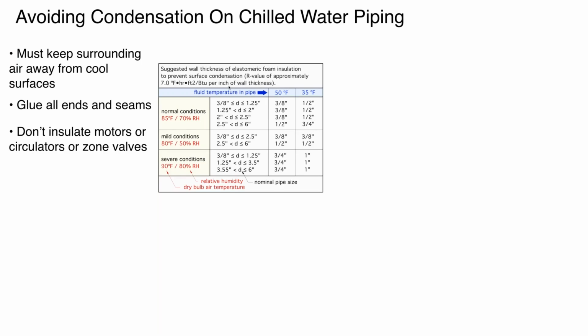This is a table that actually came out of, I believe it was, idronics number 27 or number 30. And it shows different insulation thicknesses of elastomeric foam that would prevent condensation depending on the chilled water temperature and also what kind of dry bulb and relative humidity.